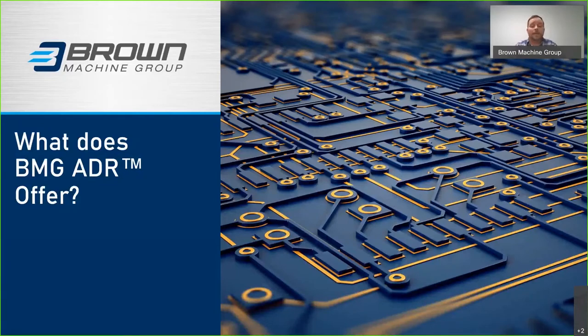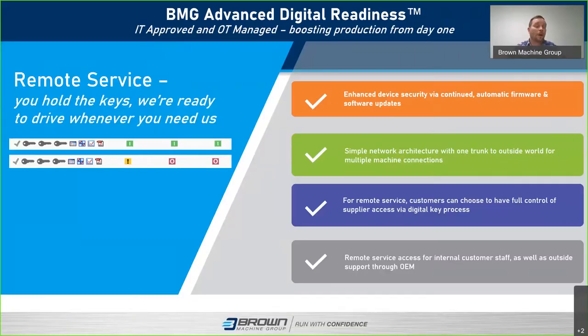What does ADR offer? Advanced Digital Readiness has several applications. Remote service is the lock-and-key aspect of accessing the machines from the IT side through to the OT side. It uses a simple network architecture with one trunk to the outside world for multiple machine connections. Through standard IP addressing, we can support up to about 40 red boxes on one green box.